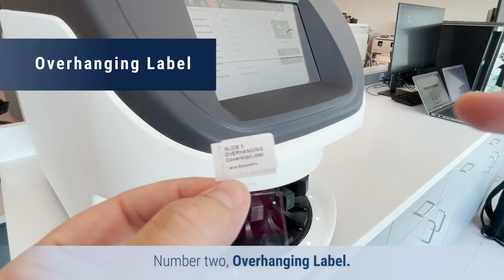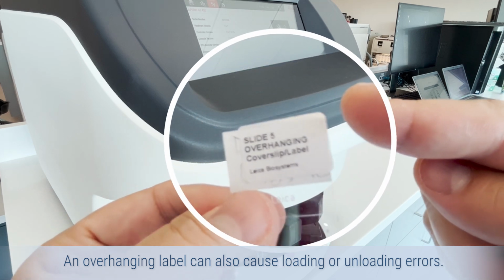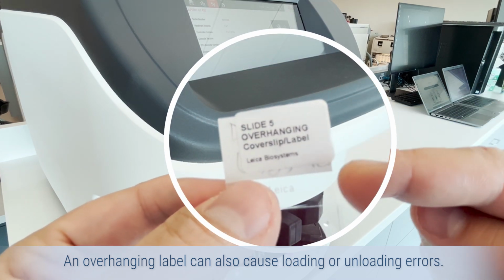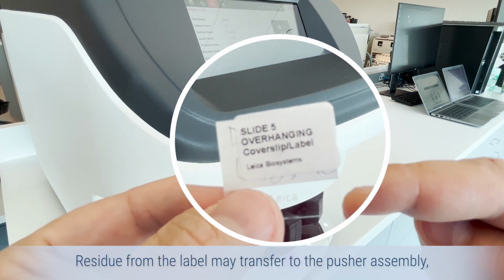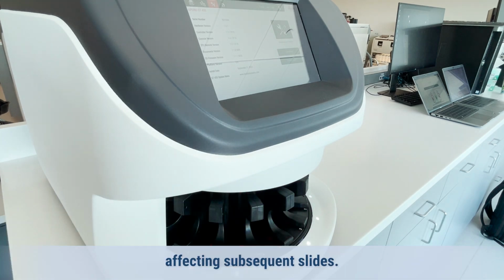Number 2, overhanging label. An overhanging label can also cause loading or unloading errors. Residue from the label may transfer to the pusher assembly, affecting subsequent slides.